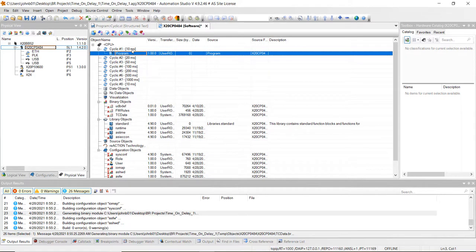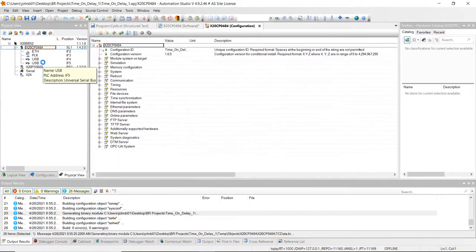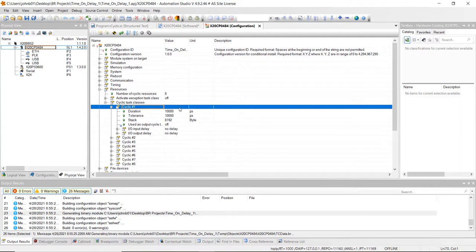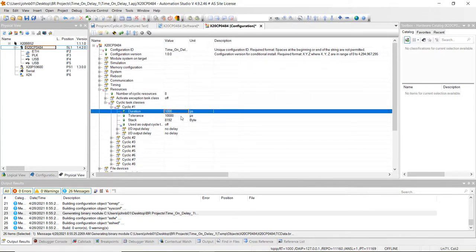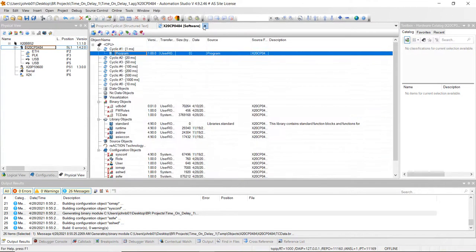We can also change the cyclic to an even faster scan time. Right click on the controller again and click on configuration, then go down to resources. Click on cyclic task classes and then click on cyclic number one. Here we can change the duration — right now it's set at 10,000 microseconds, which is 10 milliseconds. Let's change this to 1,000 microseconds and set the tolerance to zero. That means the first cyclic task class is going to be scanned every millisecond by the PLC. We could go down to 800 or 400 microseconds, but for this project we'll keep it there. Go ahead and hit save all and close out.